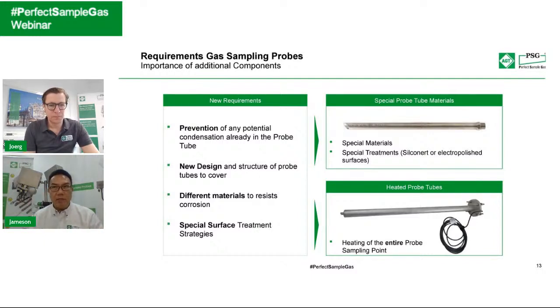Many times everybody knows we have to find the right sample tube material to overcome this situation. There are two options. One option is to use a PTFE sample tube. The other, more expensive one, is the heated tube at 180 degrees. Now, the question: which is better?